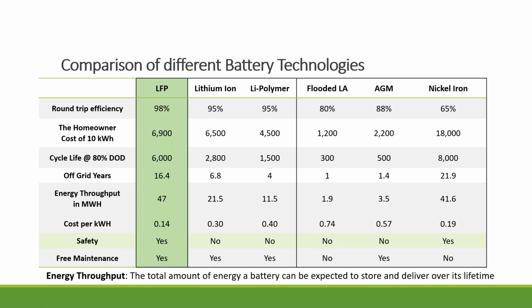Now we're going to spend a little bit of time on this comparison chart. This shows efficiency, the cycle life, as well as the total energy throughput, and then of course the cost per kilowatt hour. Because again, that's a true apples-to-apples comparison. Starting with the LFP chemistry, it has very good round-trip efficiency, 98%, so you only have 2% loss. The other lithium family is a little bit more, at 5%, and flooded and AGM is somewhere between 80 to 90%, depending on the manufacturer and some more advanced technology. The nickel iron is pretty low, really only 65%.